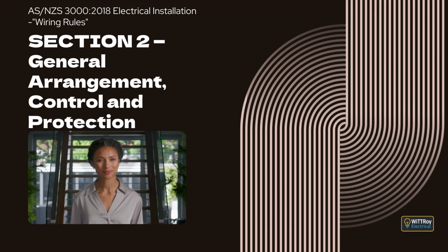Section 2.5.7 Reliability of supply. Clause 2.5.7.1 General. This part explains that an electrical installation should be arranged so the supply stays as reliable as possible. To do that, the installation is divided into sensible circuits, and the protective devices are chosen so they discriminate properly. That means if a fault happens on one part of the installation, only the device closest to that fault should operate. The rest of the installation should stay energized. The idea is to minimize how much of the supply is lost when a protective device trips.